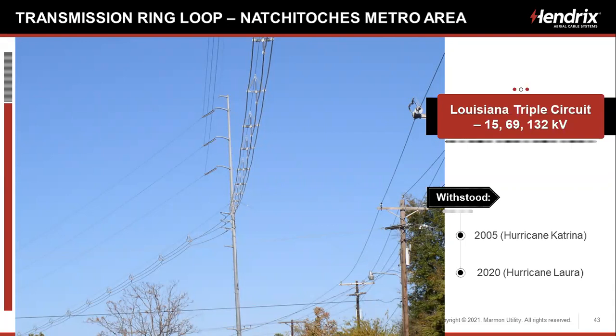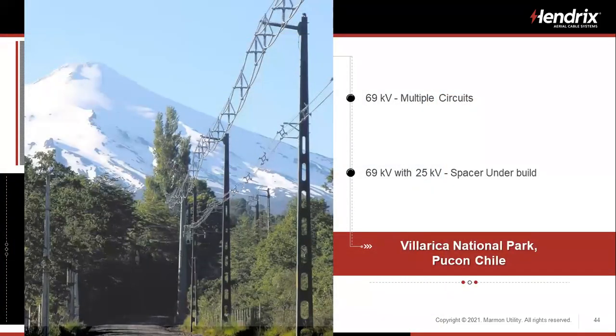And oddly enough, as soon as we installed that, it was hit by Hurricane Katrina in 2005, bent up a couple of spacers, but it survived. And then it was hit again last year with Hurricane Laura. So we're very happy with this system, and it's performed admirably in the face of severe weather. Get back to the system that we have in Chile. This is quite scenic because there's a famous volcano. There's a famous area for vacationing. So what we did here, we had 69 kV on top, and we put a 25 kV spacer cable underbuilt below that.